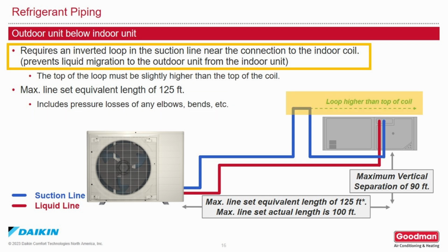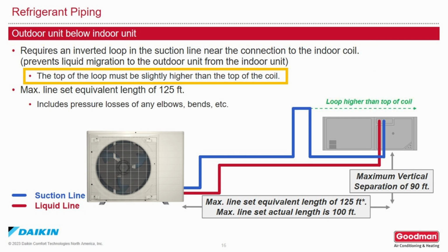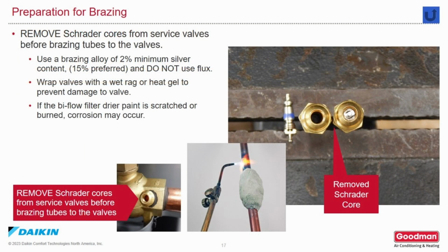Also note that the suction line must have an inverted trap with a loop that extends higher than the top of the indoor coil. Preparing for brazing, make sure you remove the Schrader core so that they won't melt from the heat of brazing the line set. Always use a brazing alloy with a minimum of 2% silver content. 15% is recommended. Never use flux. Wrap all the valves with a wet rag or heat gel to prevent damage to the valve.